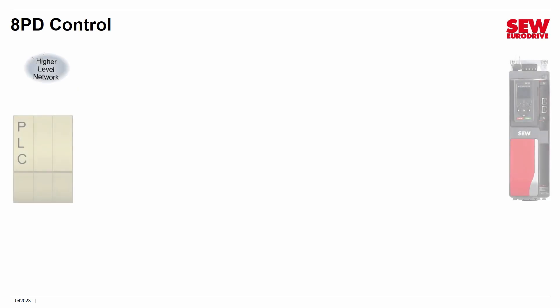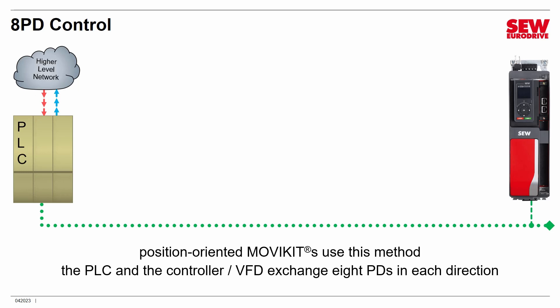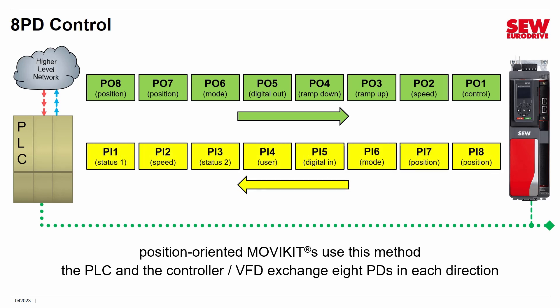There's also an 8PD mode, commonly used with position-oriented MOVIKITs that need extra process data words. The first five POs match 5PD — control word, speed, ramps, and digital outputs. PO6 selects the positioning mode, and PO7 and PO8 carry the target position. On the return side, PI1 through PI5 match 5PD, PI6 indicates which mode the VFD is in, and PI7 and PI8 carry the current position. Additional classes covering field bus control in more detail may be offered in the future.